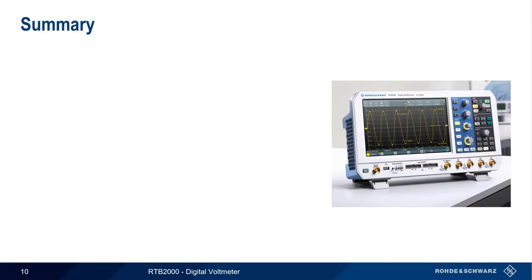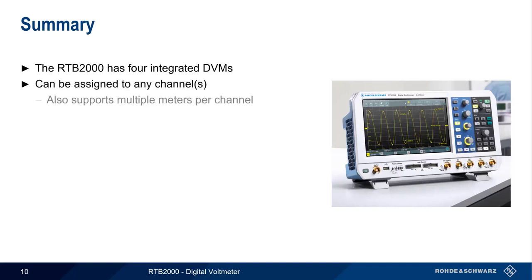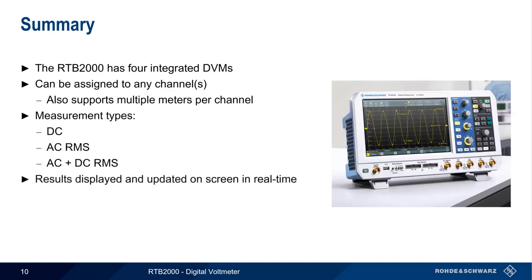Let's end with a brief summary. The Rohde & Schwarz RTB2000 oscilloscope supports four integrated digital voltmeters, and these voltmeters can be assigned to any of the active channels. Multiple meters can also be assigned to a single channel. The supported measurement types are DC, AC RMS, and RMS of a combined AC and DC signal. The results are displayed on the screen in real time in a small movable window. And note that in addition to having a graphical user interface, these DVMs can also easily be configured and monitored using programmatic control.